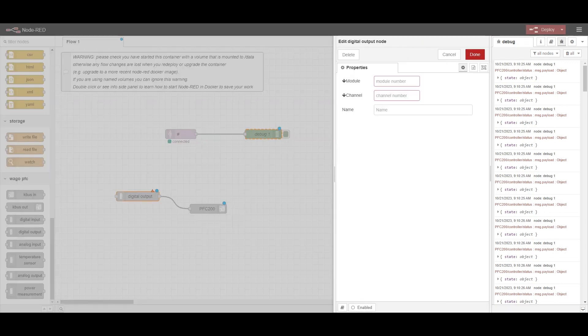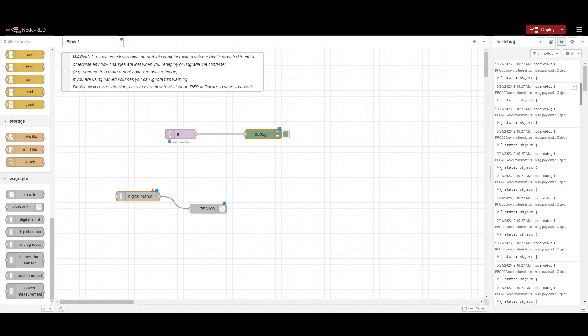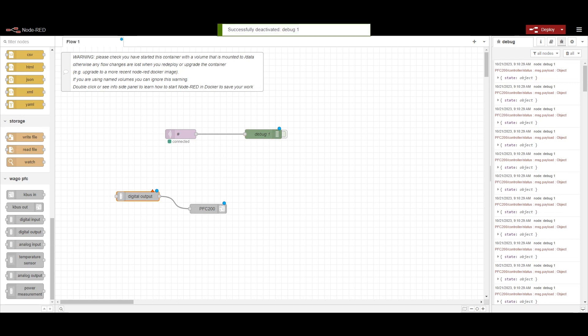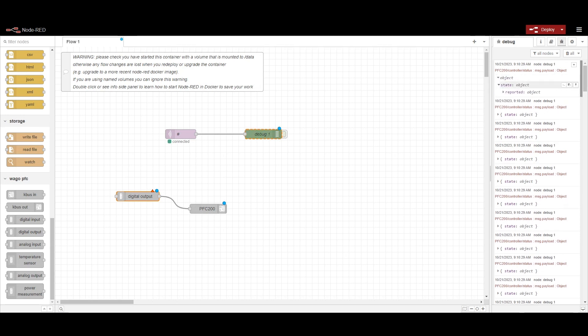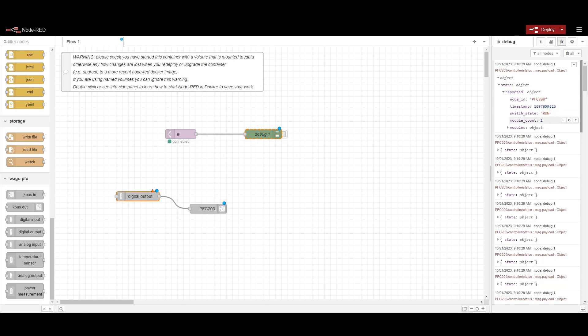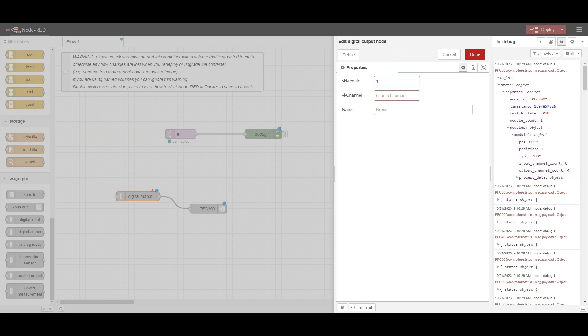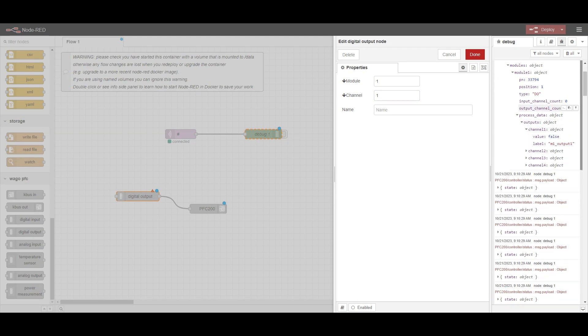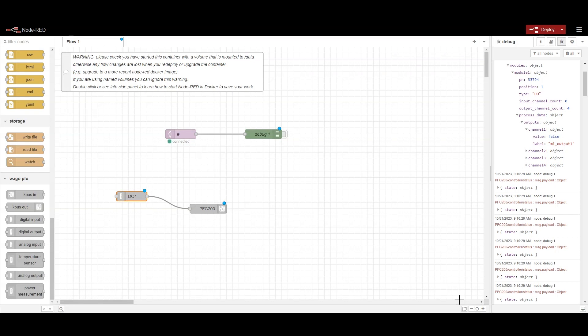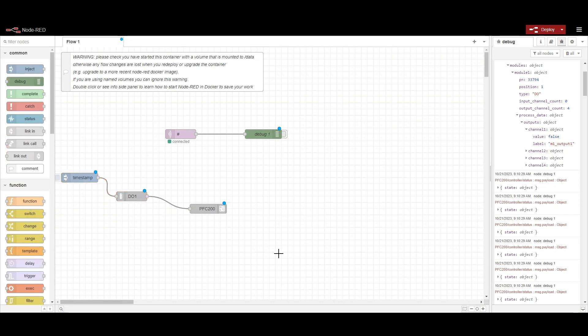For the digital output we also need to provide the module number. Checking the debug output, we can see the module count is one, and in the module detail the position is 1 and the type is 'DO' (digital output). So we set module ID to 1. For the channel, the card has 4 channels and I am using channel 1. We give it a name and these basic configurations are all that is needed.